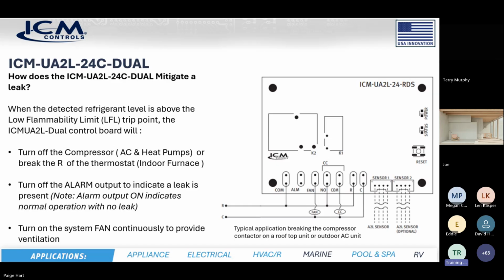So you can see here, this is your typical application for an outdoor unit. You see now, this is a little bit closer. You can see where you have the ability to connect two sensors. And then you can see where the fan is connected to the fan terminal, and the compressor contactor. So basically what's gonna happen is, as soon as you reach what they call the low flammability limit trip point, it's sensed enough where it says, okay, there's a leak. And then what it's gonna do is turn on the fan, turn off the compressor, and turn off the alarm LED, so that you know that there's a leak and you gotta take care of it. Your fan will be running, the light will be out, so something's wrong. You gotta fix that leak.